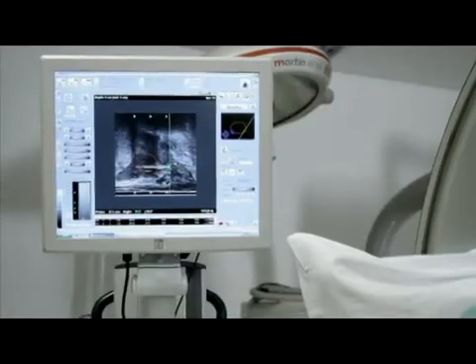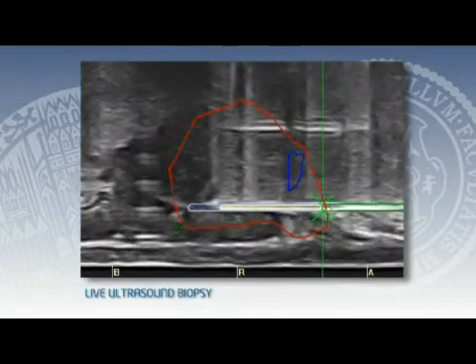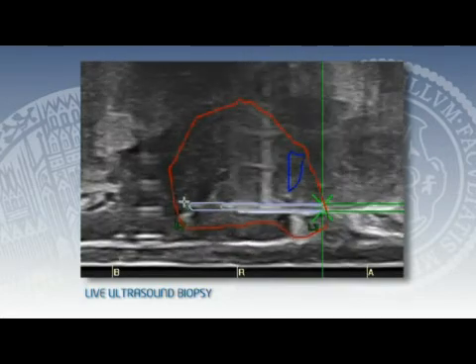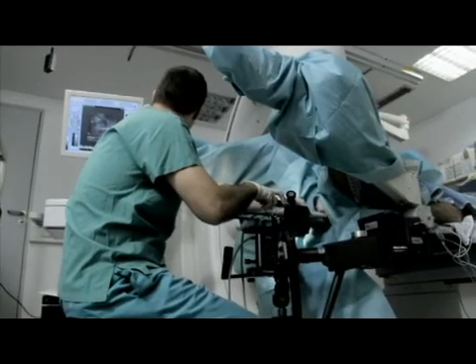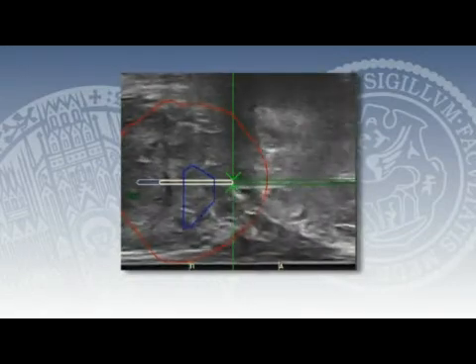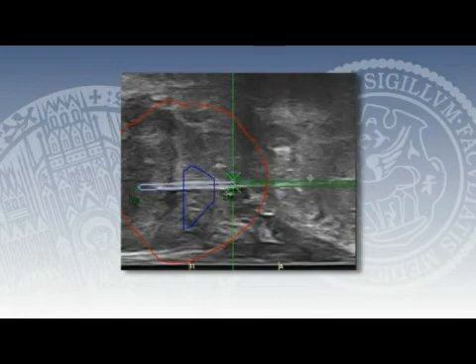During the following phase, the user selects the desired biopsy cores one after the other, and rotates the ultrasound transducer until the longitudinal plane crosses the virtual needle insertion line. The physician then inserts the needle under continuous longitudinal ultrasound guidance. Due to a long longitudinal crystal array, the needles are visible immediately when entering the perineum, and long before penetrating the prostate capsule. The ultrasound image is overlaid by organ and lesion contours, as well as the planned needle trajectory. Thus, real-time navigation is established so that deviations from the target become instantaneously visible on the screen and can be corrected early, enabling needle positioning with high accuracy. Organ shifts during needle insertion are equally visible and can be adjusted as needed.